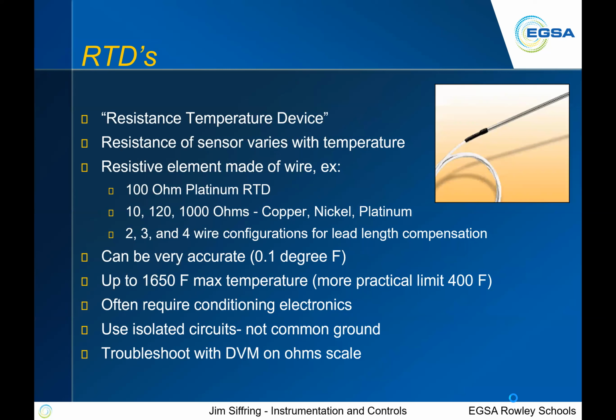RTDs, resistance temperature devices. As opposed to the thermocouple that gives a voltage out, which is proportional to a temperature, these things actually change resistance with the temperature. So that's the difference between thermocouples and RTDs: one changes voltage output, one changes resistance. They can be made out of all kinds of different materials that give you all kinds of different resistances. Platinum, copper, nickel, platinum, and they can be in different configurations.